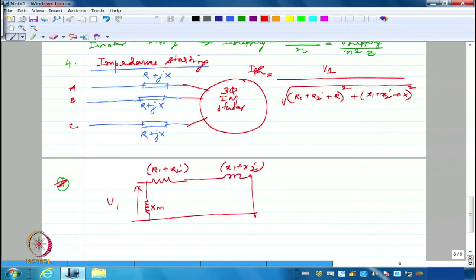So if I look at the power factor of the motor, it will not be very good during starting condition also, because you have R1 plus R2 dash. R2 dash is generally small, squirrel cage induction motor, thick rotor bars, so I will not have much resistance. R1 might have some amount of value, and X1 and X2 dash, I am really not going to have very small value because there is air gap. Leakage is going to be somewhat pronounced. So X1 and X2 dash actually are going to be the leakage values which are somewhat larger. Xm actually is also going to draw a good amount of current because I have air gap. I can't help it. So we will see normally that the starting power factor is not good. Starting power factor of an induction motor is not good.